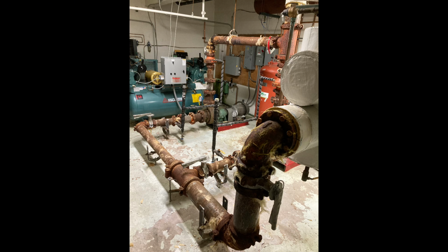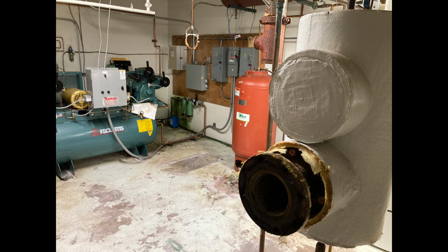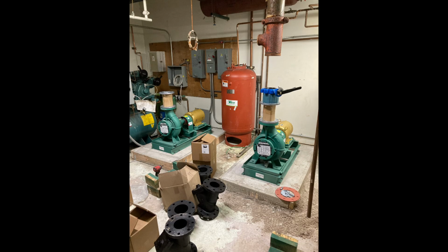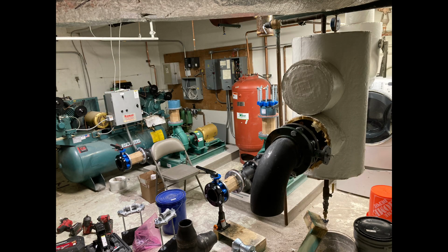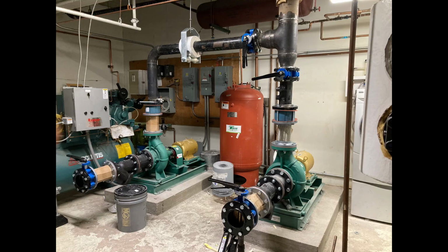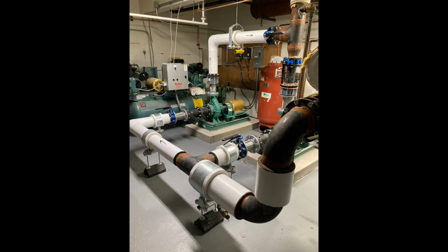Here's the current piping with the insulation removed and the water pumps down in the basement. So the guys removed the old water pumps and old piping. And they poured a new concrete slab for each of the new pumps, installed the pumps, made sure they're level. You can see the welders getting everything welded up in place. New valves, new piping, new insulation.